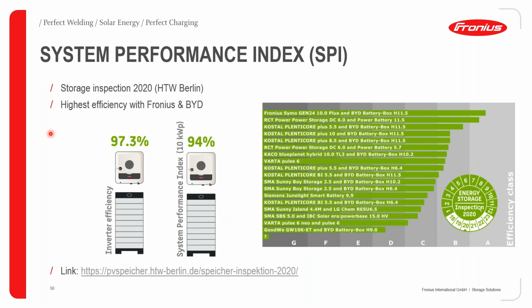As already mentioned, there is an independent test that was done for the Gen 24 inverters, and Fronius actually achieved very good results in this test. From this link, you can download the entire test document that was written after the test. The combination between Fronius and BYD achieved the highest efficiency in the market so far. In terms of the inverter efficiency from the Gen 24 side, we can achieve a maximum on the higher side of 97.3%. And when you're talking about the system performance in combination with the BYD Battery Box, we are talking about a very good efficiency of up to 94%. This is for a system that was tested using 10 kilowatt peak. All the other inverters that are compatible with the BYD Battery Box came second to Fronius in terms of energy efficiency for this kind of configuration.